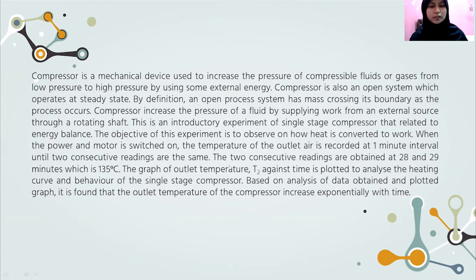This is an introductory experiment of single stage compressor related to energy balance. The objective of this experiment is to observe how heat is converted to work. When the power and motor is switched on, the temperature of the outlet is recorded at one-minute intervals until two consecutive readings are the same. The two consecutive readings are obtained at 28 and 29 minutes, which is 135 degrees Celsius. The graph of outlet temperature T2 against time is plotted to analyze the heating curve. Based on analysis of data obtained and the plotted graph, it is found that the outlet temperature of the compressor increases exponentially with time.